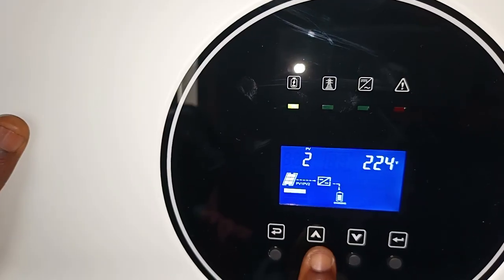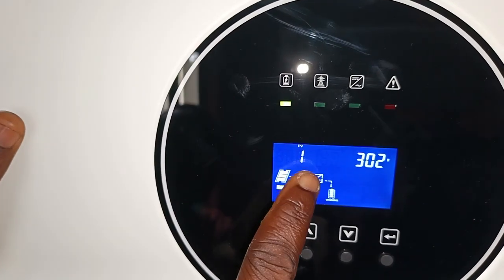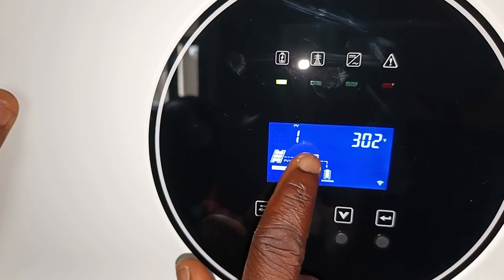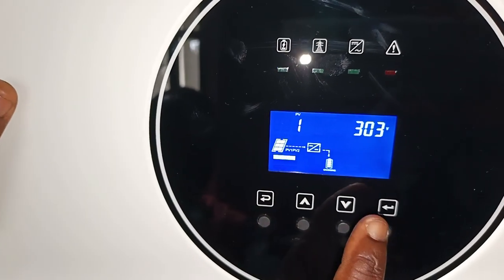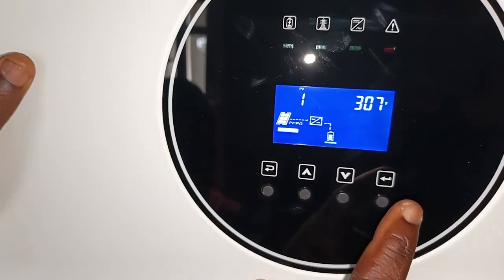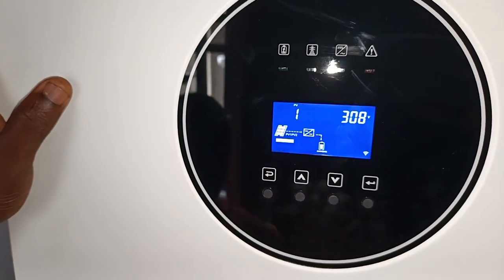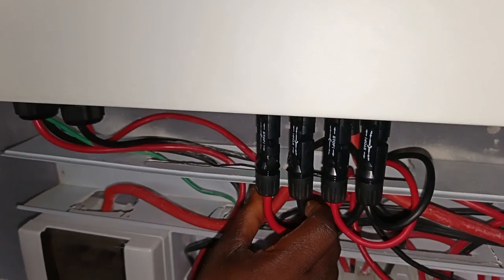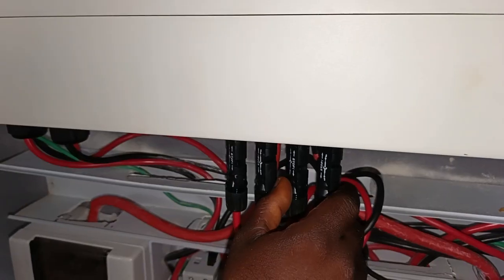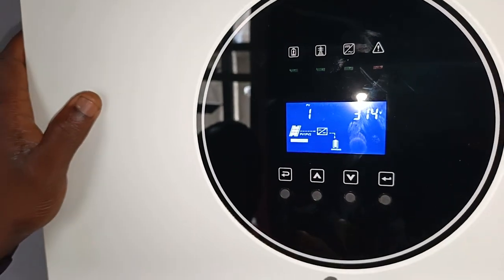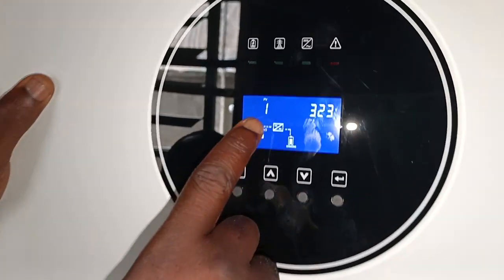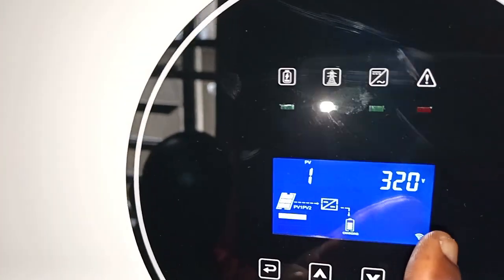This is the PV voltage. When you see PV1 voltage, it's 302. What the installer did before, he connected 15 panels, so we made one string 8 panels and the second string 7. So the voltage is going to be different. In PV1, you may see around 290 something. So this is PV1 at 322 volts.